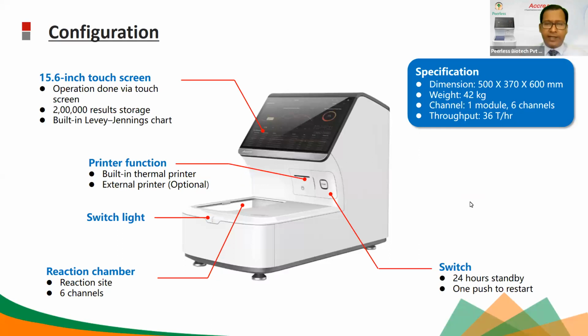It is not a very big instrument. Half of a medium-sized computer table, or a small computer table, is good enough to place the instrument. It's not a very heavy machine, the weight is 42 kgs. As we said, there is 1 module and 6 channels, and the maximum throughput is 36 tests per hour if 10-minute protocols are followed in the machine. So that is what it is. 6 into 6, I mean 6 tests per batch, that is 36 tests per hour. That is the protocol we follow.